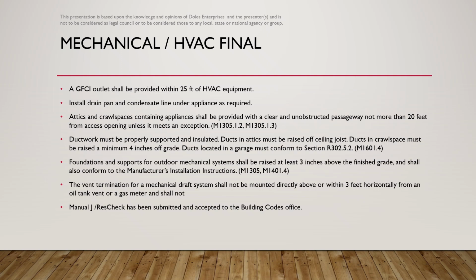The vent termination for a mechanical draft system shall not be mounted directly above or within 3 feet horizontally from an oil tank vent or a gas meter, and shall not be closer than 3 feet of an interior corner formed by 2 walls perpendicular to each other. Manual J, Res Check systems, and all paperwork shall have been submitted to the Building Codes Office or made available to the inspector at the time of the final inspection.